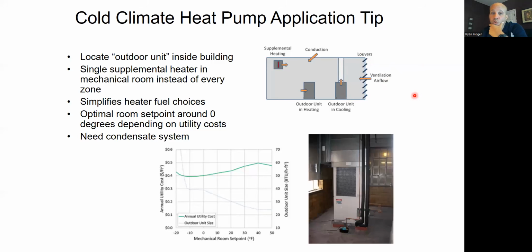Then what they do is when it gets colder and colder outside, they can modulate these dampers a little bit more down, so it sucks less air in, and instead uses air from the room a little bit more. But more importantly, they can install heaters in that room, either electric resistance heaters or even gas-fired heaters in that room. And now this heat pump is pulling its heat from that room. And instead of being 0 degrees outside, it's 30 degrees in the room because that supplemental heater is adding heat to that room. It sounds kind of hokey.